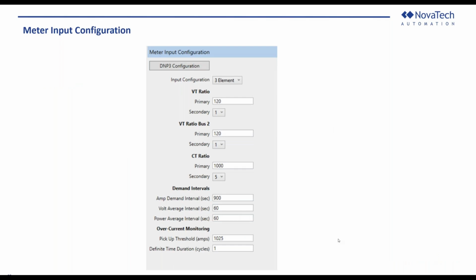The input configuration by default is 3-element. It can be chosen by drop-down to either 3, 2, or 2.5, depending on how you're wiring, whether it's a Y or a delta. It allows users to configure their PT and CT ratio. For illustration purposes, I have PT ratios being set to 120:1 and CT ratio being 1,000 amps to 5 amps. Also, the user can configure the demand intervals.